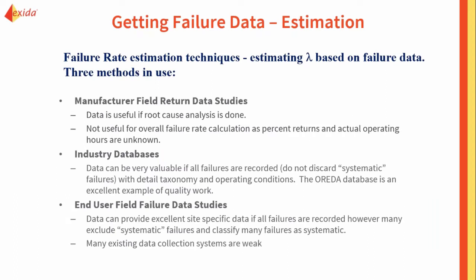So in estimation, reliability engineering says that you can estimate failure rates from field failure reports using statistical techniques and analysis, if the analyst also has a good understanding of the equipment operation, of the component failure modes, of all key environmental variables, of how the equipment is being used, and of how the data is being used by the designers.